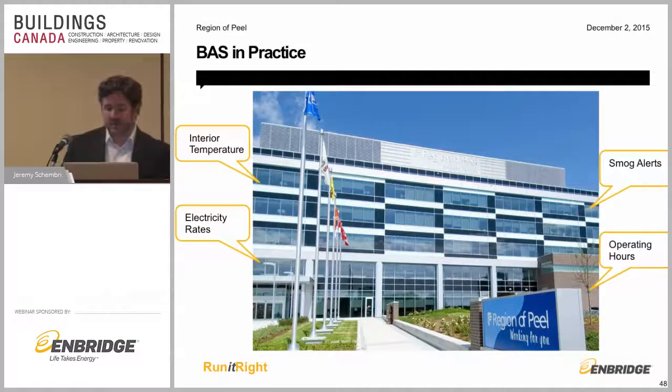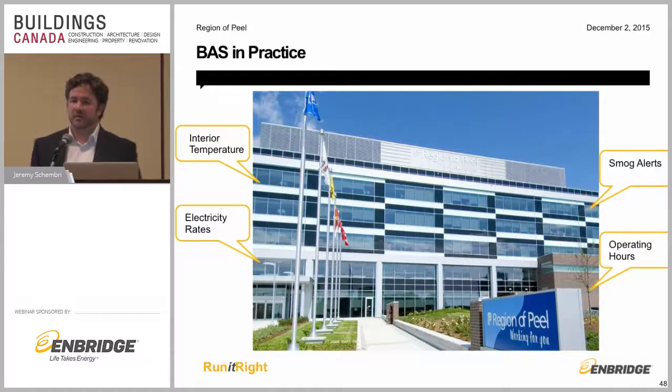So, BAS in practice. There are some of the obvious things that we use our system for: ensuring that interior temperature is set for the comfort piece, ensuring that we're running on appropriate operating hours and ramping up based on schedule. But we've also tied into, like I mentioned earlier, electricity rates. We spend a lot of money and energy, and a lot of it's for pumping water. So if we can figure out ways to take advantage when the electricity rates are low, to pump water to certain spots, then wait and pump water again to different storage areas, and have those triggers tied into our system from the province, it allows for significant savings for us. And we're talking millions. This is a $27 million portfolio. So if we can find even percentage points, it has significant savings and pays us back.